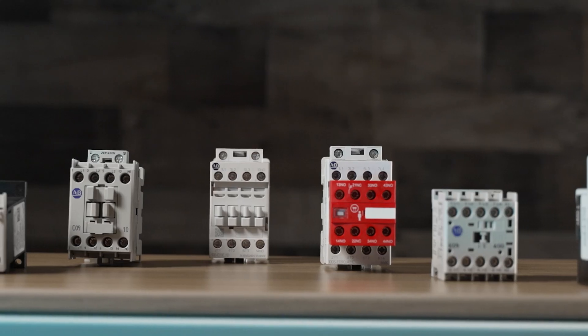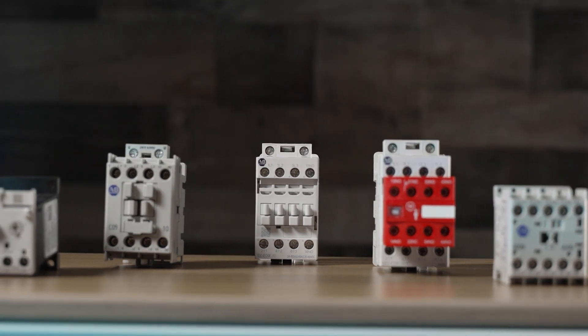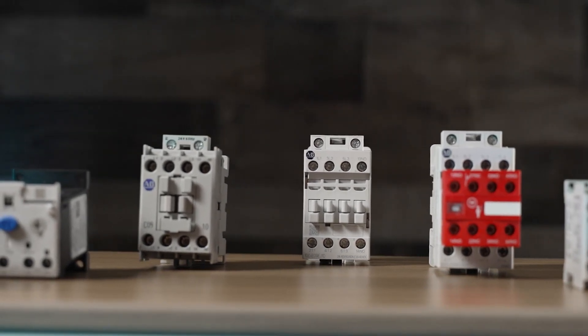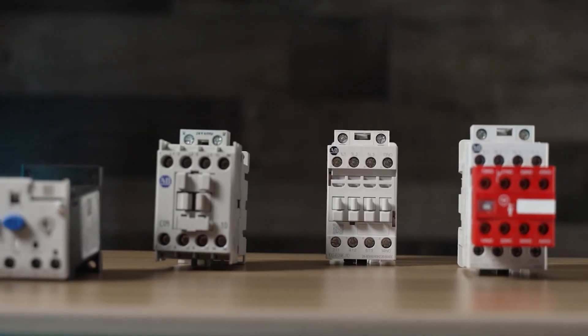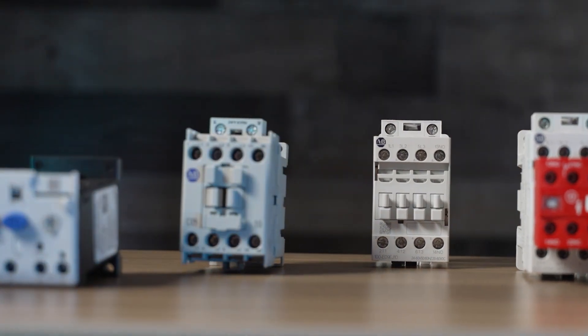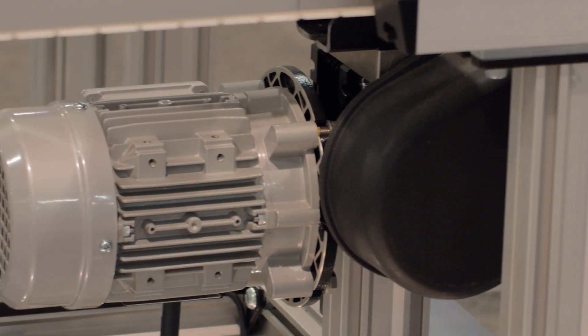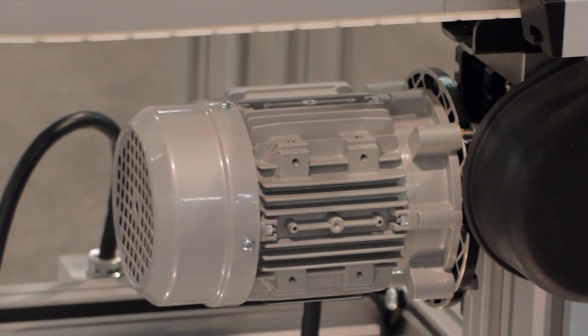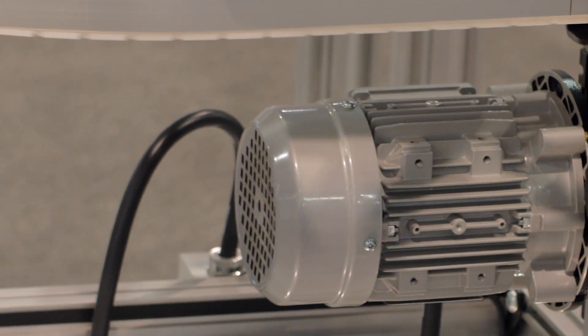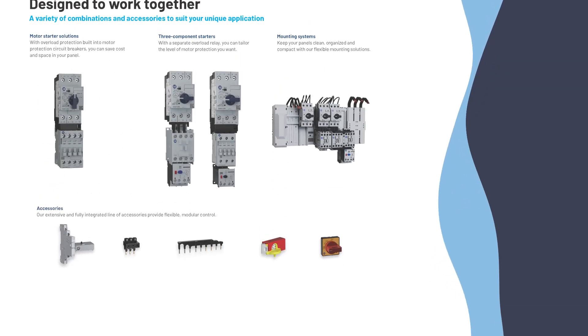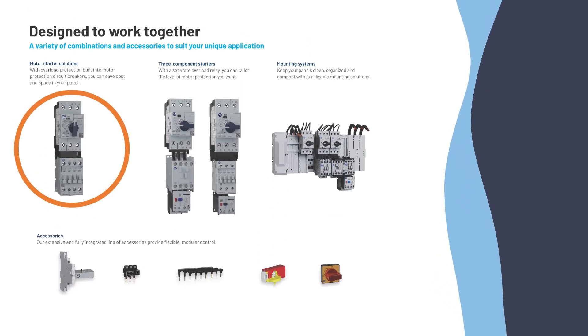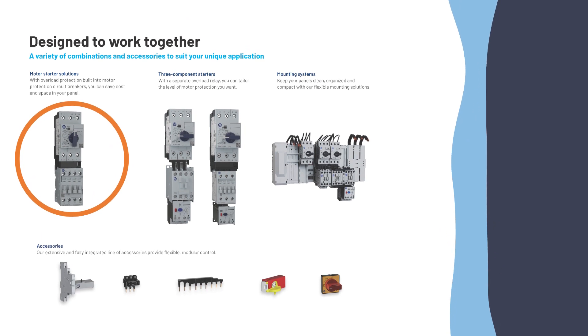Across-the-line motor starters remain ubiquitous in industrial applications despite the proliferation of solid-state motor start technologies. The former, along with complementary circuit breaker and relay components, energize and de-energize motors of all sizes while protecting against overload. Consider multi-function starters with breakers for short circuit and thermal overload protection, two very different threats to a rotary electric motor.